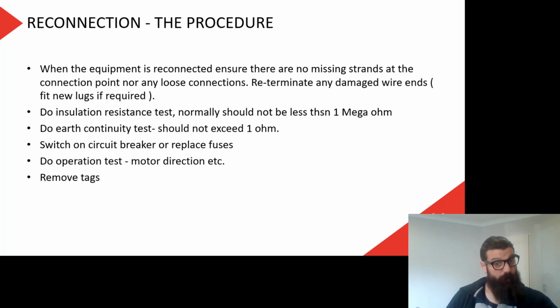Switch on the circuit breaker, so we turn the power back on. Obviously we unlock it first. We do our operation test. We make sure that the equipment is now working, because I promise you will feel like a dork if you switch everything back on and then walk off, and the customer rings you later and says that thing is not working. And then we take away any of our tags and we're done.